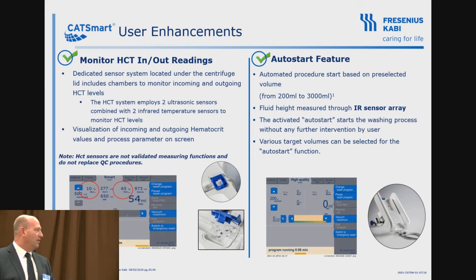We then have an auto start feature. Most all auto start reservoir holders on the market are weight based, so if you lean on it, it kicks in, or you push it up against something. This is an infrared array on both sides, so it's looking at red cells, and it won't kick in if it just has saline. So you put your number in there, between 200 and 3 liters, and it'll automatically kick on. You can always press the manual start, and it'll start processing. So that's a very reliable way of measuring that.